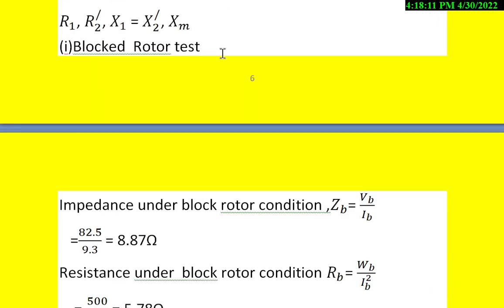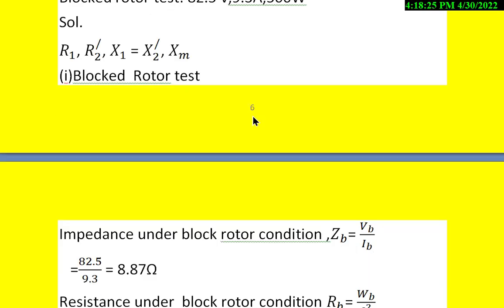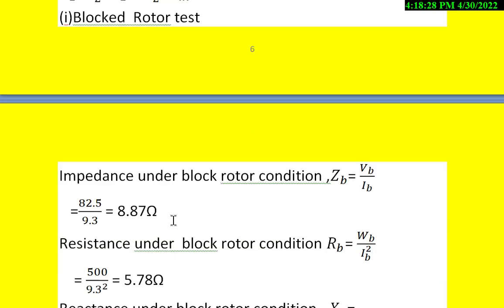From the blocked rotor test, we know the formula: ZB = VB/IB. VB is 82.5V and IB is 9.3A. After simplification, ZB = 8.87Ω.